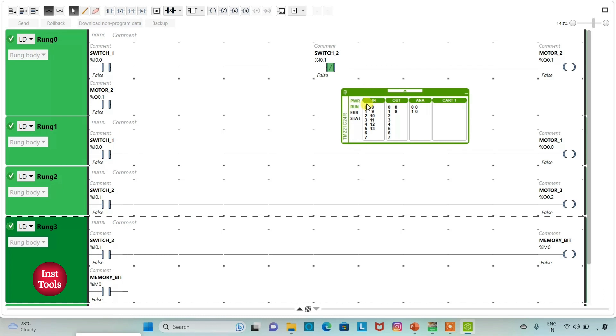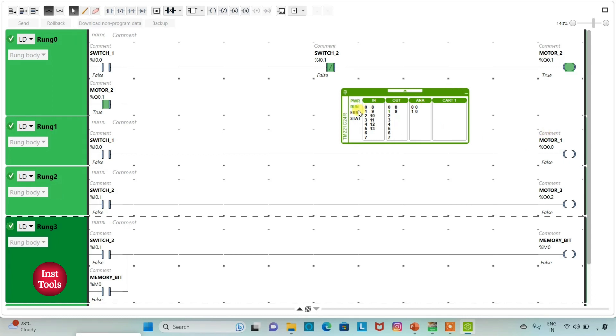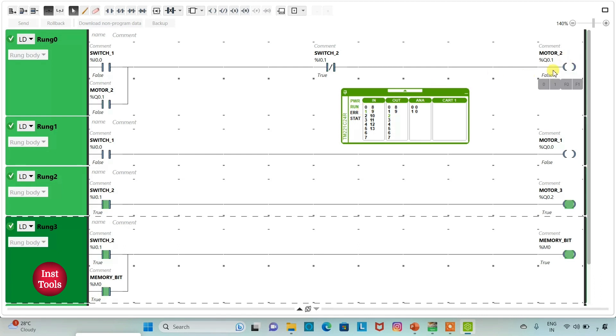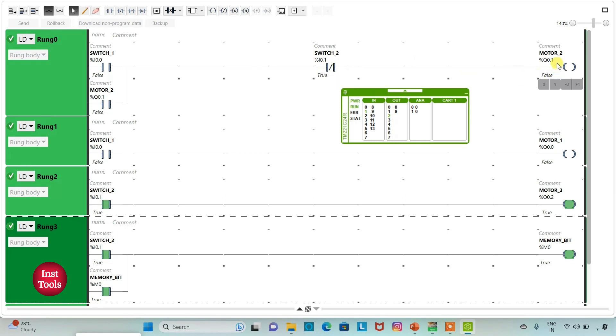When I turn on switch 1, motor 1 and motor 2 will be on. When I turn off switch 1, motor 1 will be off but motor 2 still remains on. And then when I turn on switch 2, motor 2 will be off, as we used a normally closed contact — when switch 2 is on, current will not flow through it, and motor 2 will be off.